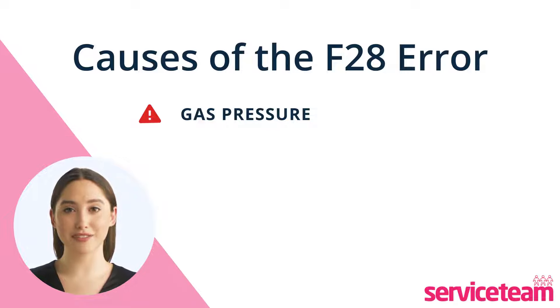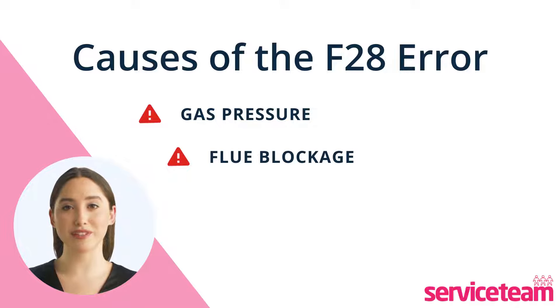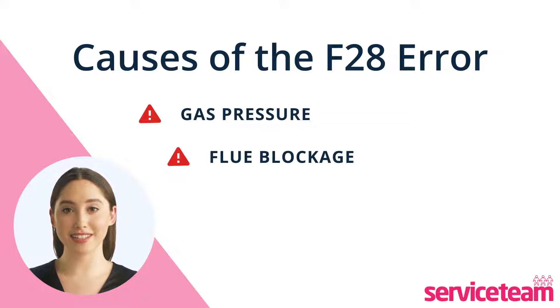An F28 fault can occur due to a blockage in the flue, where exhaust gases are released, or in the condensate pipe. These blockages can result from wear and tear over time, so it's best to consult a boiler professional for a comprehensive repair.